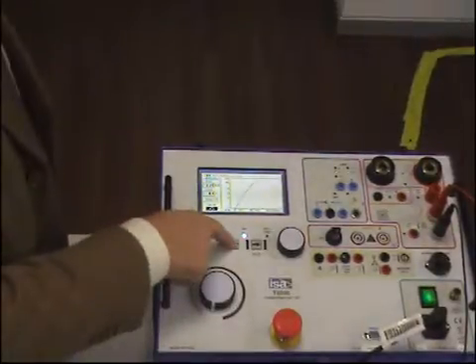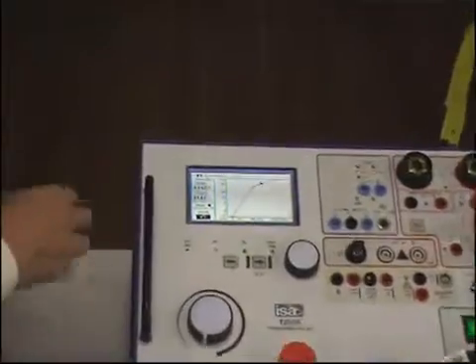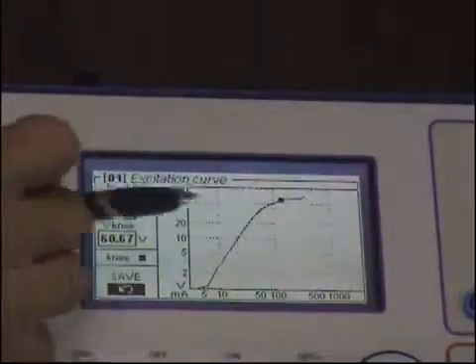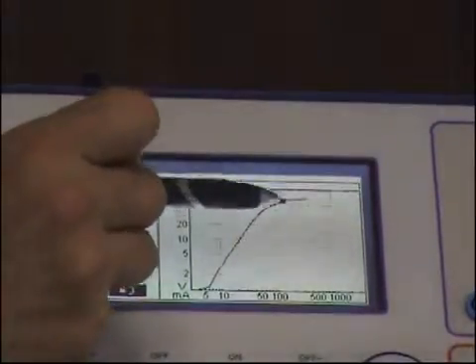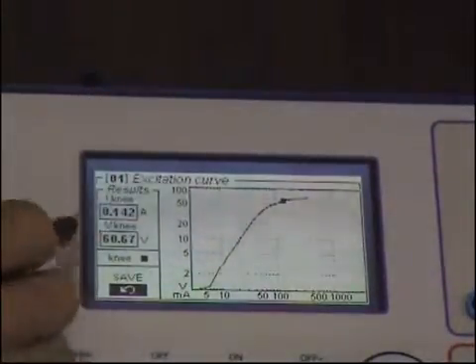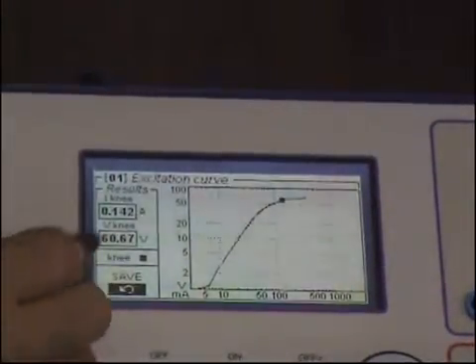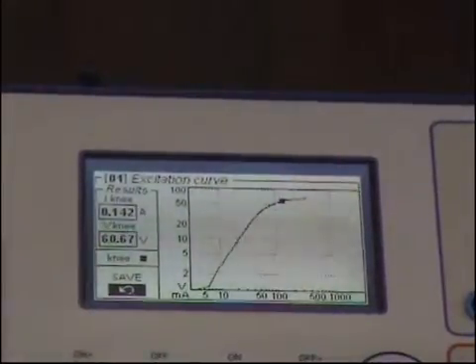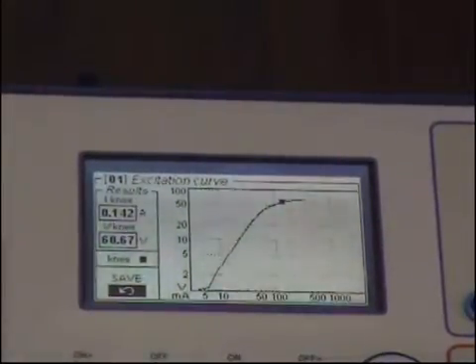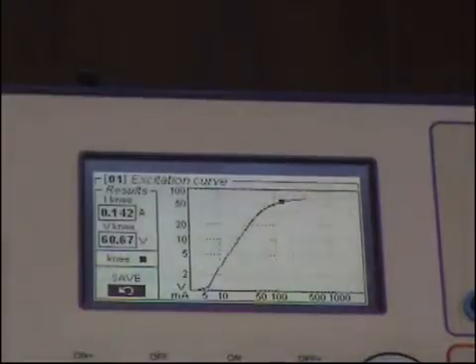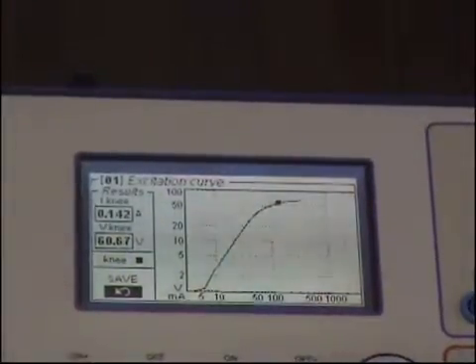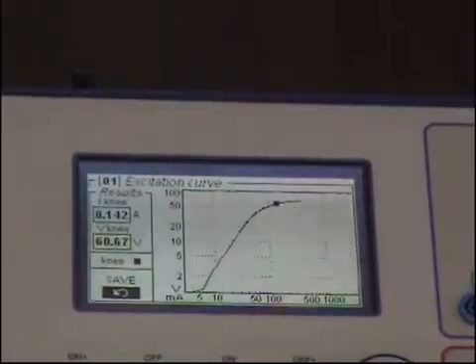Now, as soon as I press off, I see here a black dot, and this black dot is telling me this is the knee point. The knee point has been found at 60.67 volts, which is 1% different with respect to the nominal value. The current is less than expected, and this means that this is a good transformer.